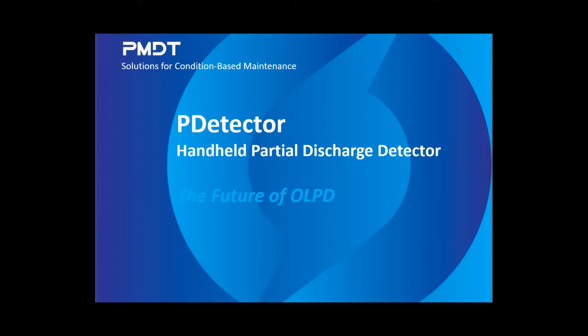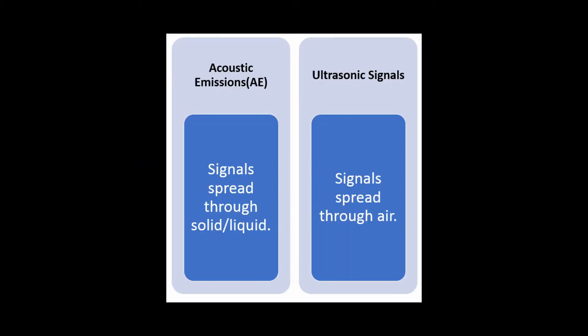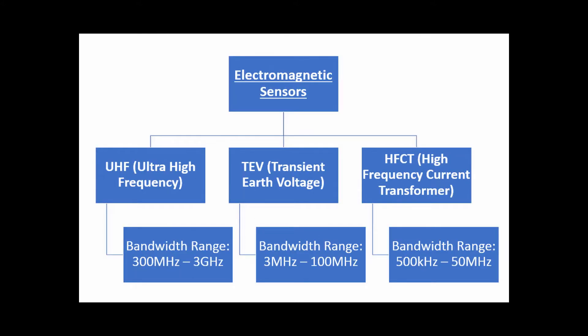The P-Detector is an advanced handheld online partial discharge detector that employs five detection methods: acoustic emissions, ultrasonic, TEV, UHF, and HFCT. The information from multiple sensors gives the P-Detector the versatility to detect all types of PD in various medium and high voltage power equipment.